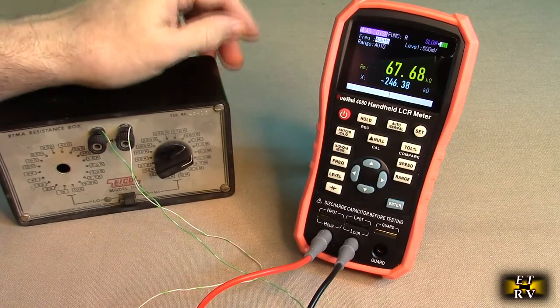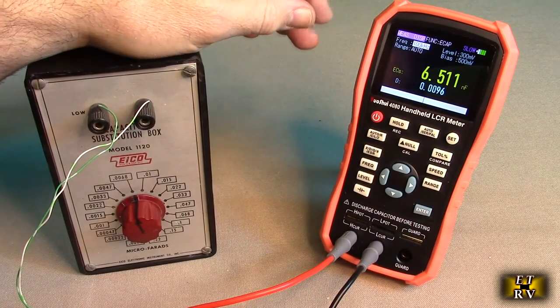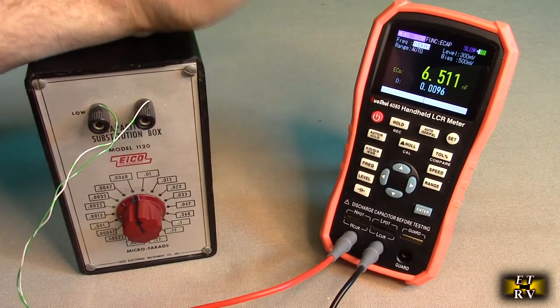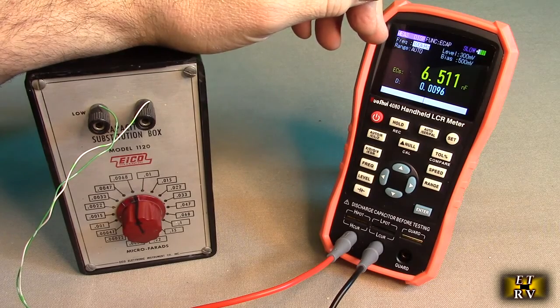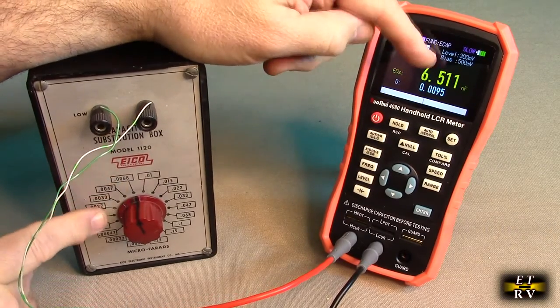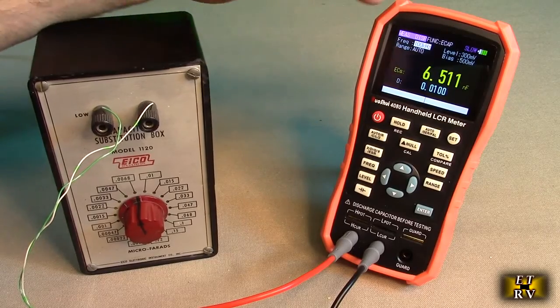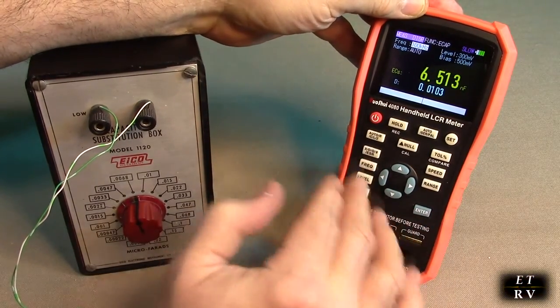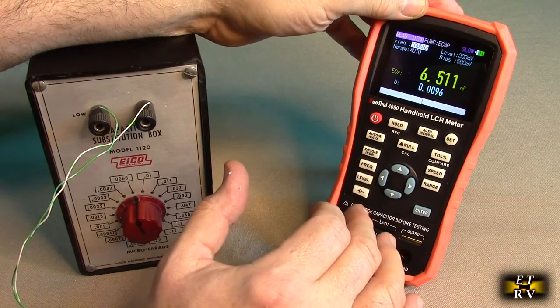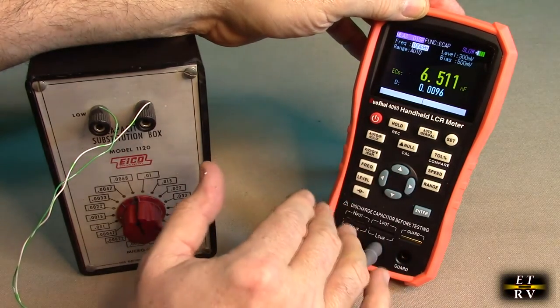Here's a capacitance box. Now you've got capacitors probably laying around in drawers which are uncalibrated. This is calibrated for testing purposes, but the great thing is that you can put your capacitors that are laying around your lab that you don't know anymore, and it'll tell you. Right here I can change the value. This is in microfarads: 0.0068, and this is 6.511 nanofarads, which is correct. I believe this more than I believe the label on here. This is at a certain frequency. That's at a hundred kilohertz. Before I started, I hit the capacitor button right there. If you hold this down, there's even a function to do electrolytic capacitors.